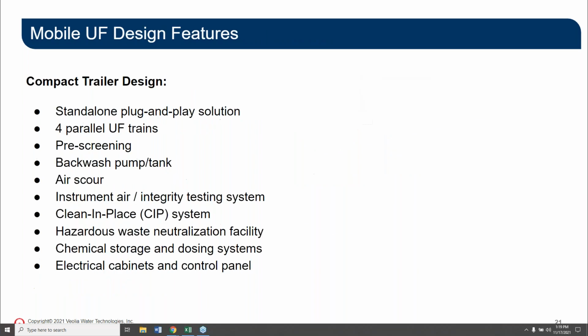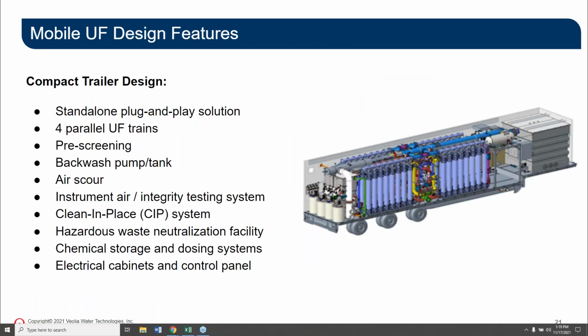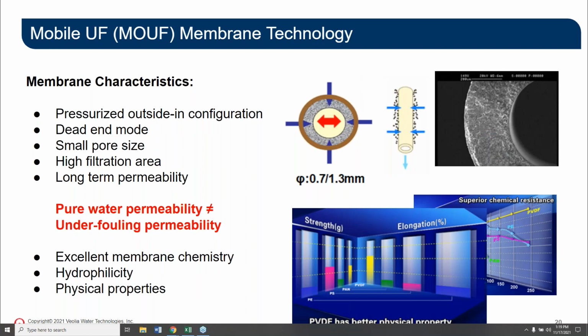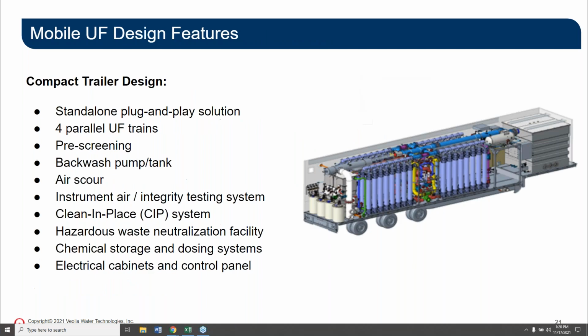Secondly, the chemistry of the membrane is a PVDF chemistry. It is highly hydrophilic, and this means that it is less prone to fouling by organics. The PVDF membrane is also known to be high in chlorine resistance, and it has a high breakage resistance as well.